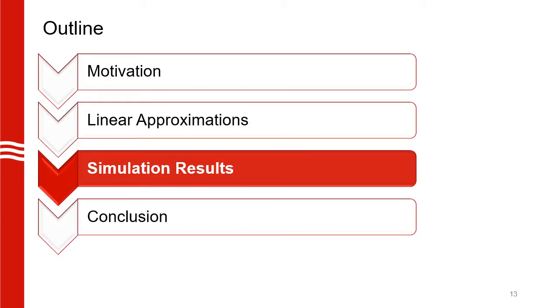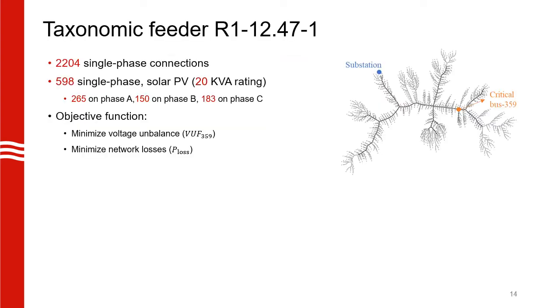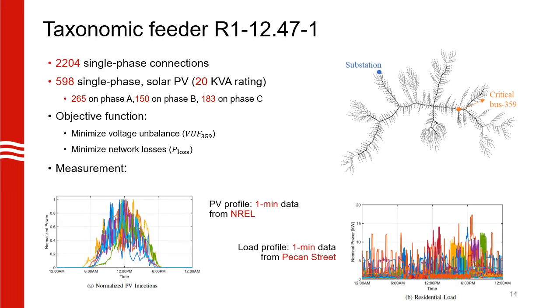Now that we have defined the three linear models, let us evaluate their performance. For our case study, we are using a large taxonomic feeder from PNNL with more than 2200 nodes. There are close to 600 houses with single-phase solar PV systems connected to this feeder. We will look at two objectives here. One is to minimize voltage unbalance at a critical three-phase node 359 as shown by the orange dot. The other objective is to minimize losses throughout the network. To model the houses, we use actual load and PV data. We have six unique PV profiles from NREL and 30 unique load profiles from Pecan Street, which are randomly assigned to all of these houses.